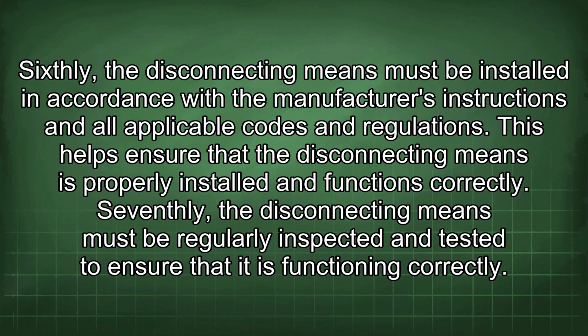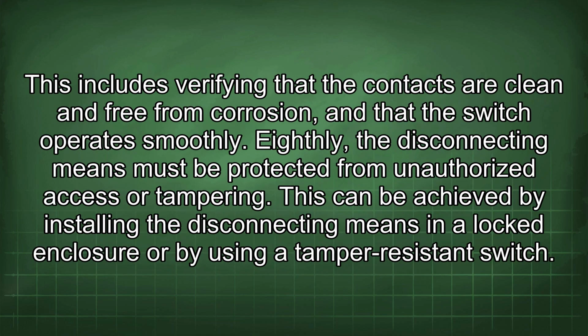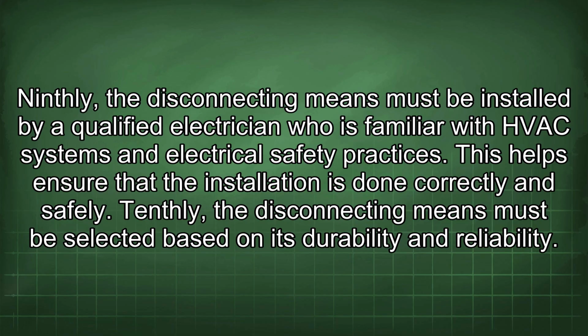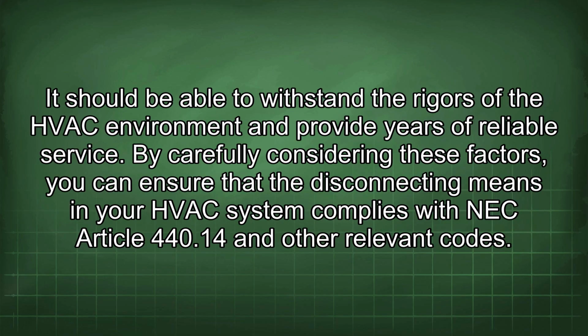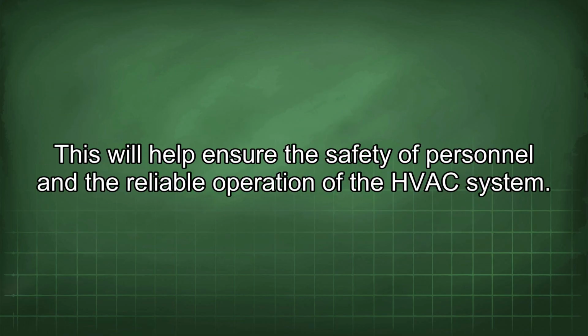Seventhly, the disconnecting means must be regularly inspected and tested to ensure that it is functioning correctly. This includes verifying that the contacts are clean and free from corrosion, and that the switch operates smoothly. Eighthly, the disconnecting means must be protected from unauthorized access or tampering. This can be achieved by installing the disconnecting means in a locked enclosure or by using a tamper-resistant switch. Ninthly, the disconnecting means must be installed by a qualified electrician who is familiar with HVAC systems and electrical safety practices. This helps ensure that the installation is done correctly and safely. Tenthly, the disconnecting means must be selected based on its durability and reliability. It should be able to withstand the rigors of the HVAC environment and provide years of reliable service. By carefully considering these factors, you can ensure that the disconnecting means in your HVAC system complies with NEC Article 440.14 and other relevant codes. This will help ensure the safety of personnel and the reliable operation of the HVAC system.